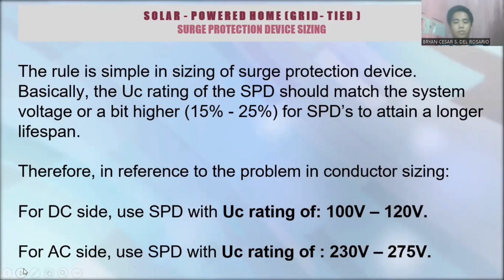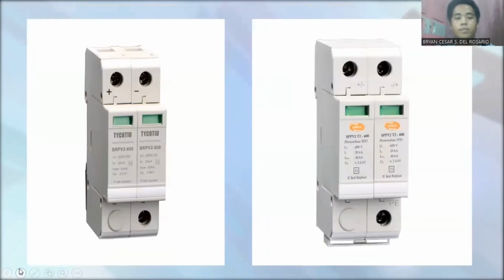Therefore, kung magre-refer ulit tayo dun sa problem in conductor sizing na kinumpit natin kanina, for the DC side, ang gagamitin nating SPD ay yung merong UC rating of 100 volts to 120 volts. So dito naman sa AC side, use SPD with UC rating of 230 volts to 275 volts. Since yung kanina is 220 volts ang standard, magdadagdag na tayo ng 15 to 25%. So gagamit tayo ng 230 to 275 volts na SPD. Merong UC rating na ganyan. So ito yung mga example na.